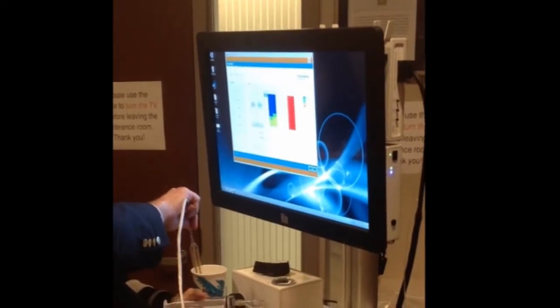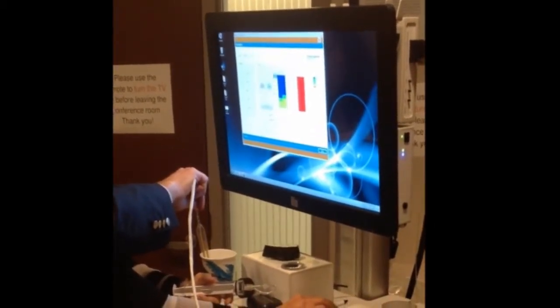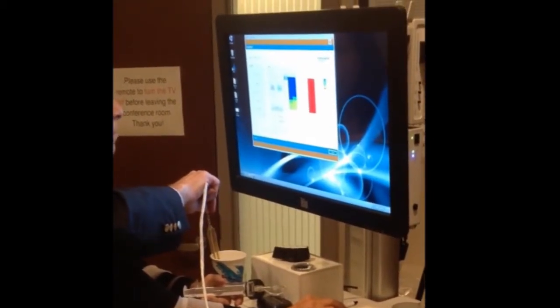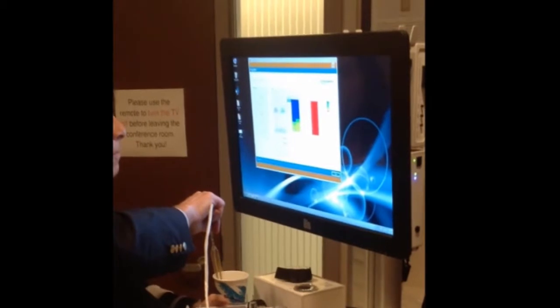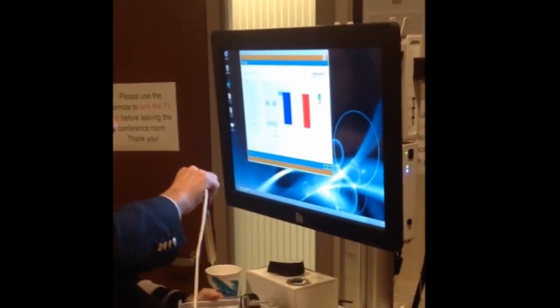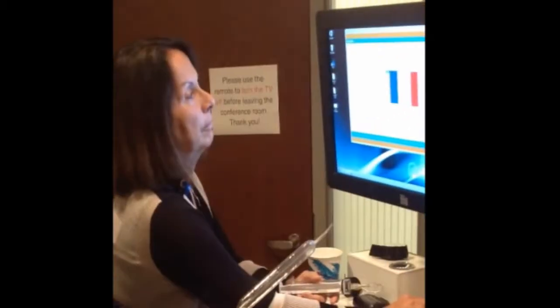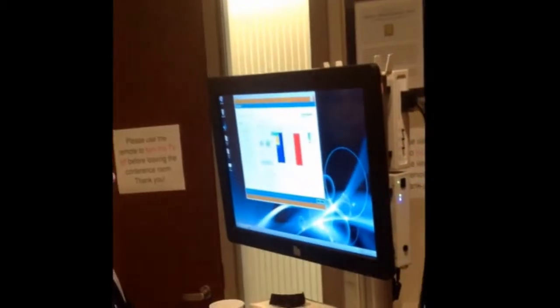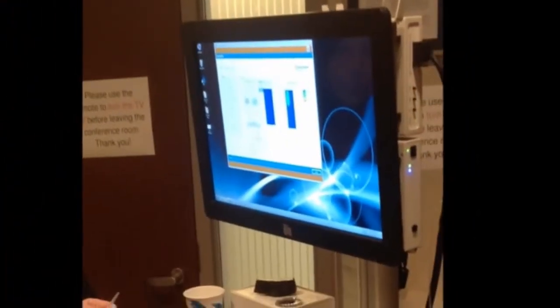And simulating as if we were in contact with fluid on the esophageal wall or in the lumen, as we dip this in, we now see the impedance change. That's because the bottom of the balloon, suggested by channels 1, 2, 3, and 4, is suspended in water. Hence the current flows and the impedance drops. Similarly, if I take it out and put it in air, the impedance will change. To show something perhaps more physiologic, I'm going to take one of the strips, but not the other, and place it on my tongue. What you should see, because of the mucosal surface, the fluid, the conductivity among cells, the impedance should drop. And then when I remove it, it goes back to infinite impedance.